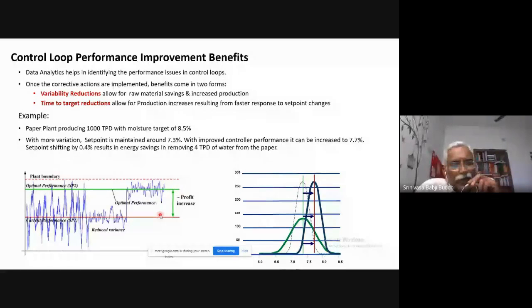For example, let us take a simple example of a paper plant producing about 1,000 tons per day with a moisture target of 8.5%. This is what is shown here. It should not have more than 8.5%. If the control loops' performance is not good, what operators will do is, this green color is the histogram, they will operate the set point far away from the limit because there is so much variation in the signals.